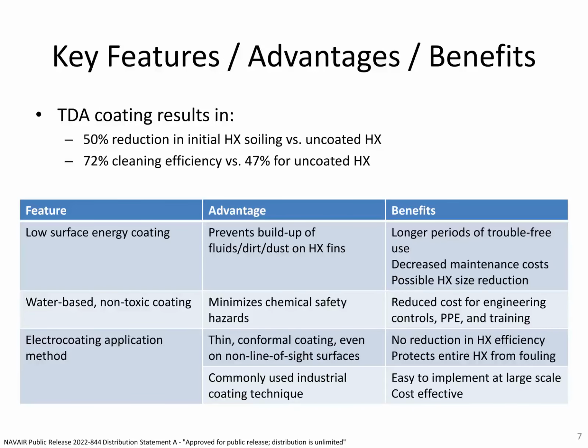Key features, advantages, and benefits. The TDA coating results in a 50% reduction in heat exchanger fouling versus an uncoated heat exchanger. This can also be thought of as a doubling in the time required between cleaning intervals. Our coating also improves the cleanability of the heat exchanger. We use a cleaning efficiency metric, which is slightly under 50% for the uncoated aluminum heat exchanger, and this metric increases to 72% for the coated heat exchanger.